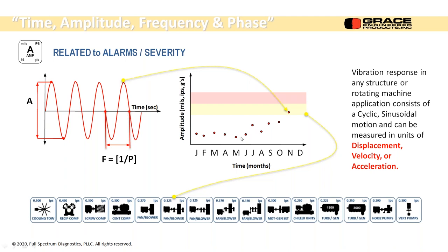But if you have a transducer that's magnetically mounted to the machine and staying put all the time, you don't have any of that manipulation. This might be actually some type of fault that popped up that's very subtle, that we'll be able to catch when we start filling in these dots with more data. So even though we're not getting any frequency information until we do a spectrum, the amplitude's got a lot of stories to tell. So we'll worry about that a little bit.